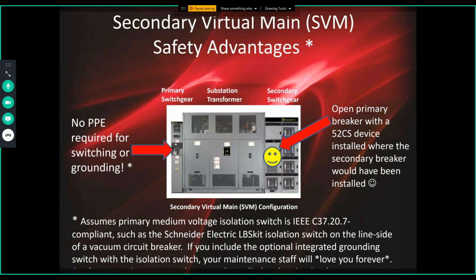Furthermore, my suggestion would be, and I could make this suggestion with or without a secondary virtual main, but it's particularly compelling for secondary virtual mains where we have a switch over a circuit breaker. As the switch is not the tripping device, you have an isolation switch and a circuit breaker, typically a vacuum circuit breaker, is to include an integrated ground switch.